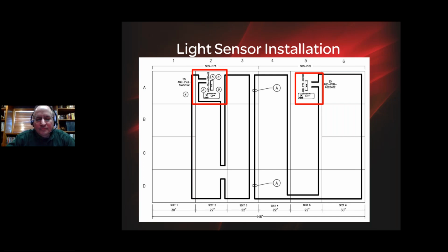Okay, next question that came in: I have a switchboard with only molded case UL489 breakers. As I understand it, these breakers have an interrupting rating, but not a short time rating. Can I install point light sensors into this switchboard and extend the protected zone into my switchboard? As long as the arc quencher unit is upstream of the switchboard, when you extend the light sensors into the switchboard it will become arc resistant.